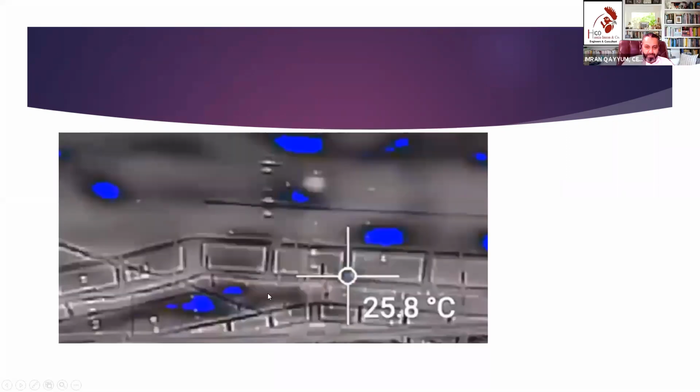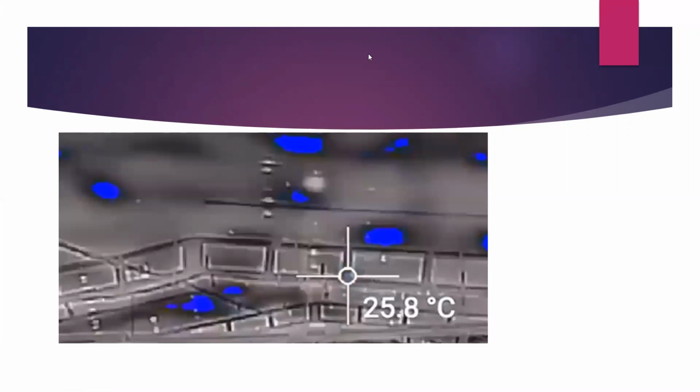In the next slide, you can see a very important picture. It is a picture taken from an IR thermal camera, and it helps us identify the leakages. Here you can see that this area is black and grayish, and this is blue. This is a leak present in the ceiling of the poultry house, and you can see it is blue. Why is it blue? Because the temperature here is very low compared to this part of the house. So there are many leaks here and there in the poultry house ceiling and inlets. The insulation is not proper.